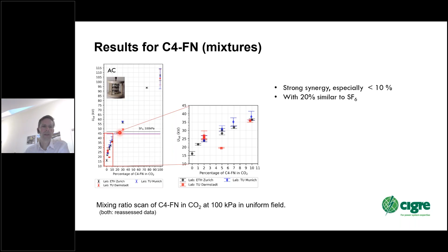First, if we look into the uniform field configuration, so actually plane-plane configuration, here you see a ratio scan at a fixed pressure. So you see the percentage of C4F7N mixed into CO2, and especially in this very low percentage region, here's a zoom of this, you see that there's a strong non-linear effect, which we call a synergy effect, which makes the increase in electric strength overproportionally strong compared to just a linear interpolation of the mixing ratios. And this is, of course, an advantage because the C4F7N can only be mixed at low percentages due to the boiling point problematic into a background gas of N2 or CO2. And for switching purposes, CO2 is used here. As a reference, with 20% of admixture, you reach the level of SF6 that was measured. And these were performed at 1 bar here.